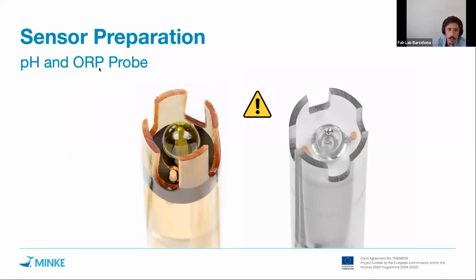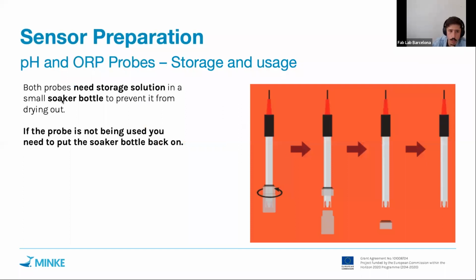In terms of the pH and ORP probes, again, they have a very delicate sensor component on the tip, which is made out of glass. You can imagine that this is quite small and delicate. They are stored in a storage solution in a small soaker bottle, and this is the sequence of opening that soaker bottle. Whenever you don't use the sensor and it's not submerged in water, you should put the soaker bottle back on. Please take care of that, because otherwise the sensor can be damaged and it would have to be reconditioned.